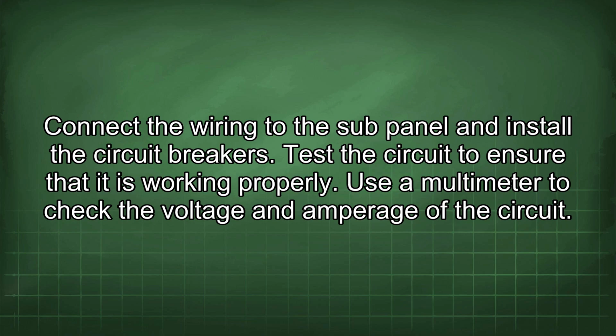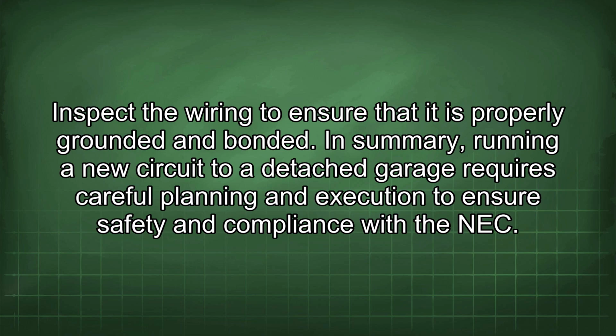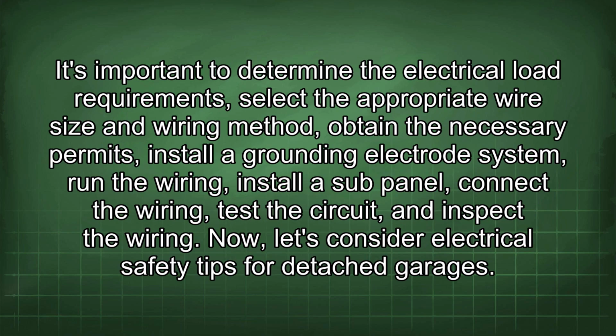Test the circuit to ensure that it is working properly. Use a multimeter to check the voltage and amperage of the circuit. Inspect the wiring to ensure that it is properly grounded and bonded. In summary, running a new circuit to a detached garage requires careful planning and execution to ensure safety and compliance with the NEC. It's important to determine the electrical load requirements, select the appropriate wire size and wiring method, obtain the necessary permits, install a grounding electrode system, run the wiring, install a sub-panel, connect the wiring, test the circuit, and inspect the wiring. Now, let's consider electrical safety tips for detached garages.